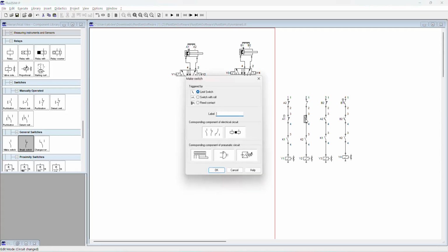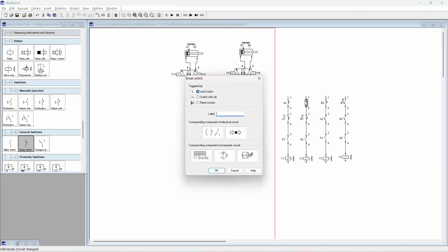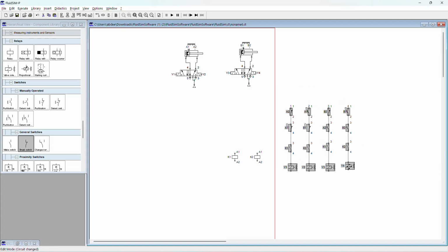All right. When do I want A to start retracting? I want A to start retracting whenever B is retracted. How can I know B is retracted? When B hits B1. And when do I want cylinder A to stop retracting? I want cylinder A to stop retracting whenever it's fully retracted. All right, so now I'm done with this sequence.